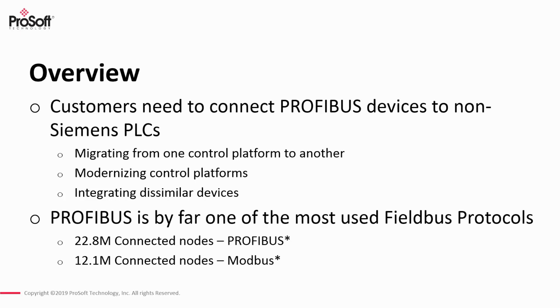As far as field bus protocols, PROFIBUS is by far one of the most widely used. Numbers vary depending on what study you look at, but one study from a couple of years ago indicated that there were 22.8 million connected PROFIBUS nodes out on various industrial control systems. Compared to Modbus, that same study said 12.1 million connected nodes. So it definitely is a widely used protocol.